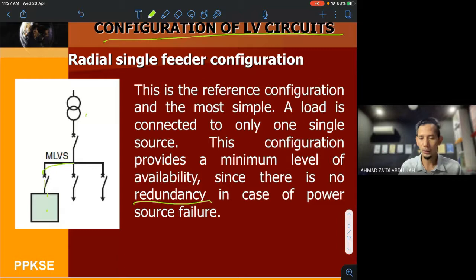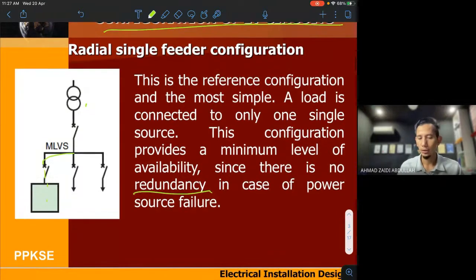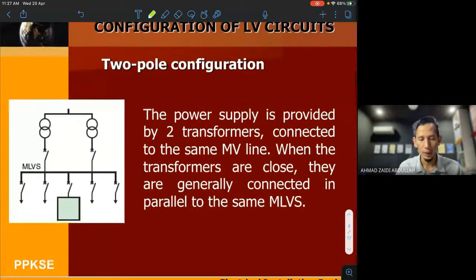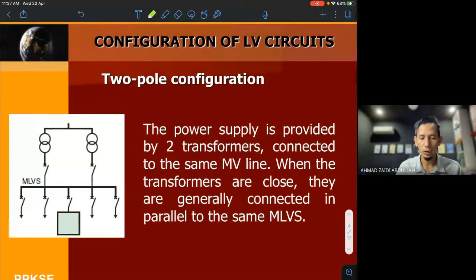No redundancy in case of power supply failure. So let's say the power supply fails, let's say TNB fails, so blackout lah. Very simple. Normally macam tu lah, our design looks like this, very simple kan. And then configuration number two is dual configuration. Dual meaning that you have two supplies. The supply is provided by two transformers connected to the same MV line. This is the MV, medium voltage, system.